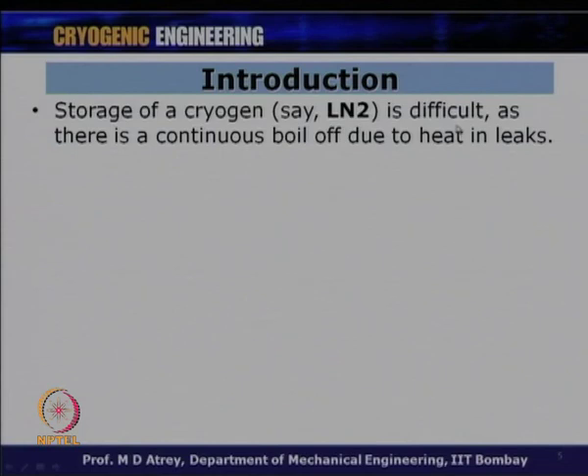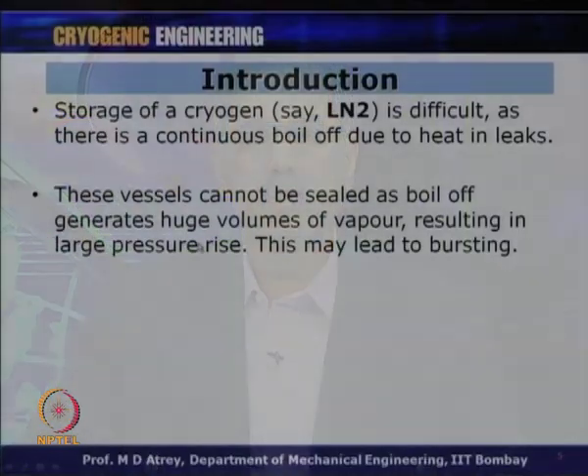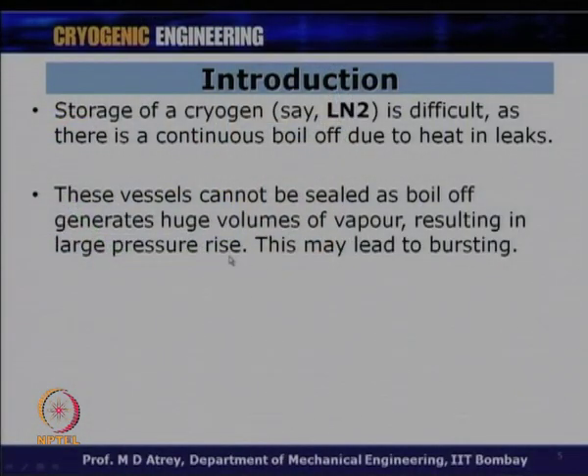Storage of a cryogen like LN2 at 77 Kelvin is difficult as there is continuous boil-off. If you see LN2 anytime, you will always see vapors coming out of the cryostat — there is continuous boil-off due to heat in-leaks. Whatever you do, you cannot prevent this boil-off; if you come back the next day, the level of liquid nitrogen will have gone down. These vessels cannot be sealed, as boil-off generates huge volumes of vapor resulting in large pressure rise, which may ultimately lead to bursting.